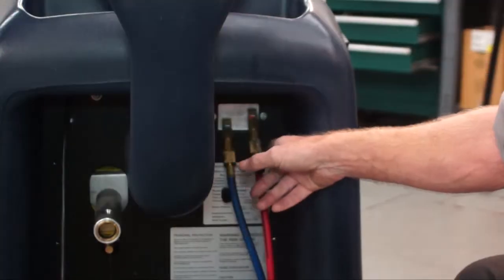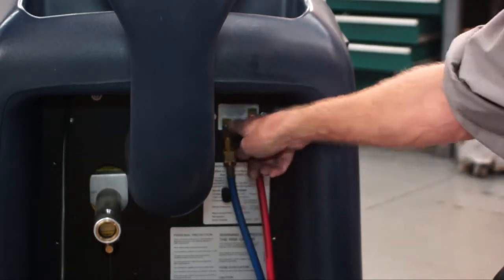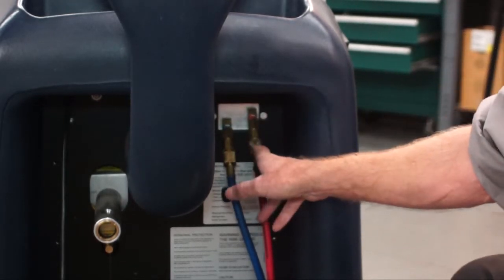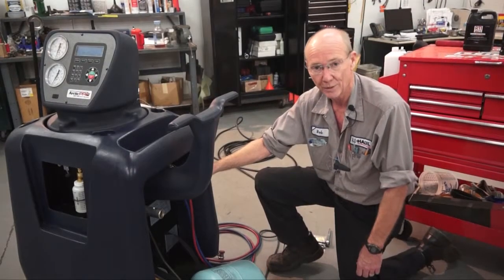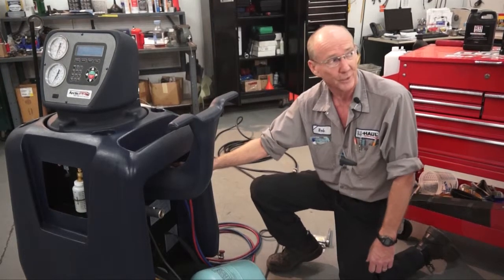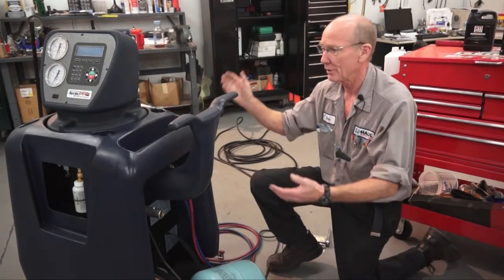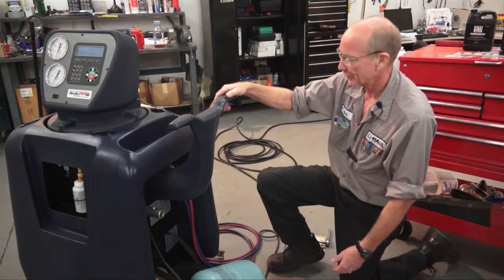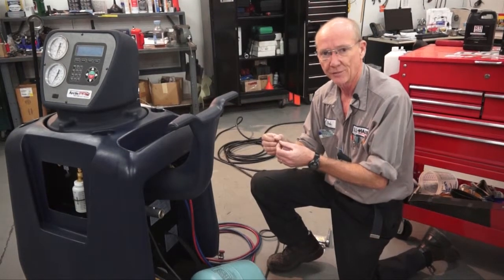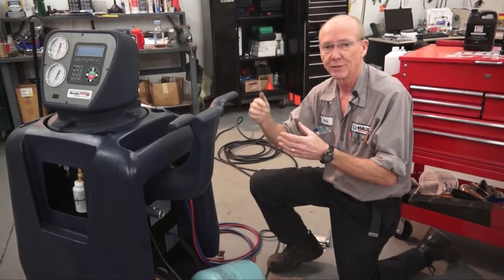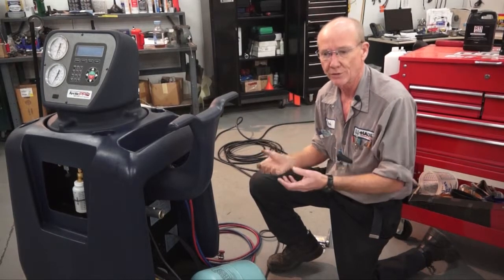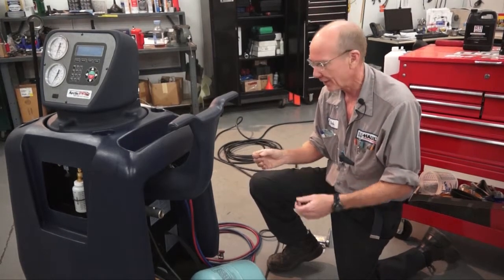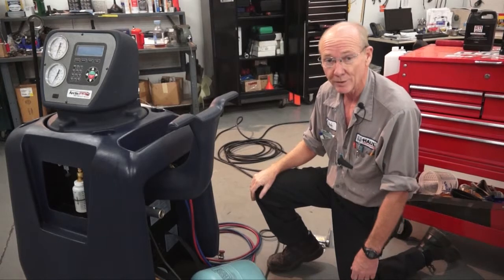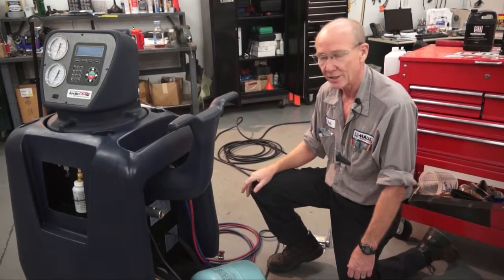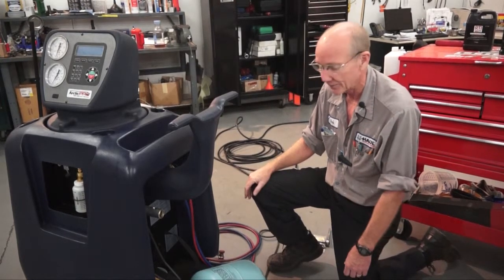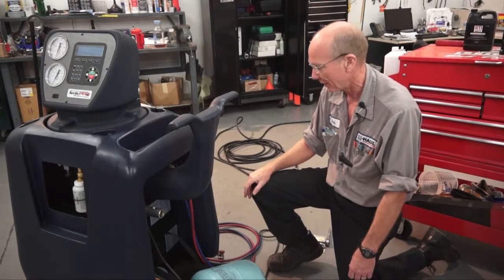It's going to carry back through into the machine. Well, it's going to collect on these inline filters that are in these fittings where the service hoses hook up. We're going to remove and replace those at the same time, because if you don't, when you recharge your system, all the debris collected on the outside of the filter can push the debris right back into the system. So I hope that makes sense. And that's why we replace those after every 10 hours, or whenever we're replacing the vacuum pump oil. Do that at the same time.